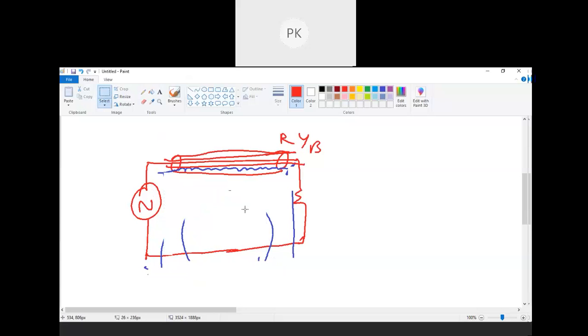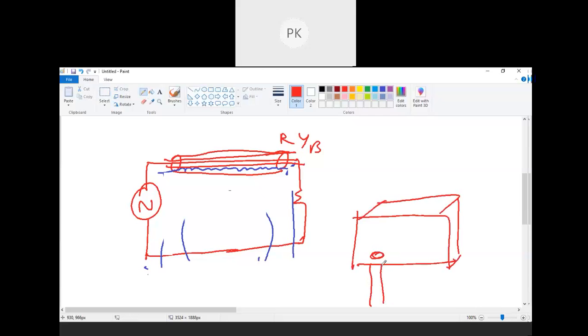Now this armor, see, normally if I have any electrical panel, at the bottom of the panel I have the opening where the cable has to come in. Now the armor of the cable has to be connected to the cable gland. That ensures there is continuity of the earthing. Okay, that is about cable earthing.